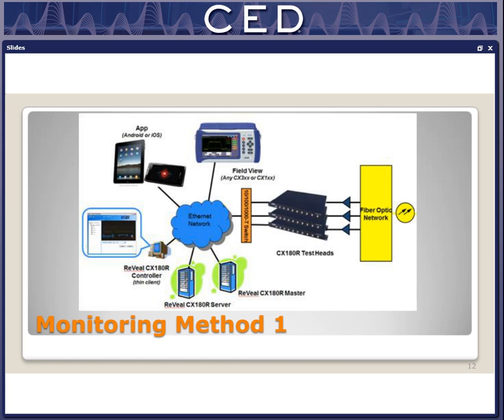It should also allow you, without disturbing the monitoring, to do on-demand tests when you try to go and hunt and repair the ingress, like Brady explained, because you need to fix it, but it's going to come back. So it's very important to have a system that allows you to have probes mounted that are available for on-demand and constant monitoring.